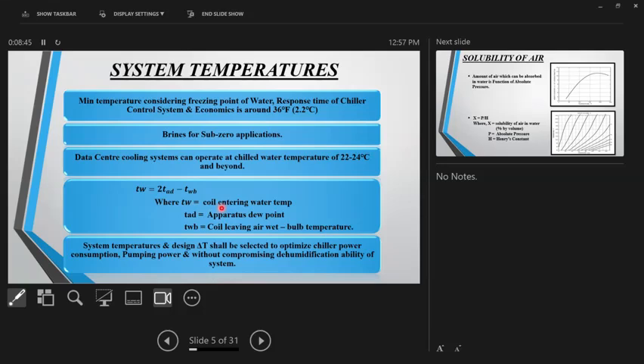TW was the coil entering water temperature. TAD was the apparatus dew point, or the anticipated coil surface temperature, and the wet bulb was the coil leaving air wet bulb temperature. So this is how tentatively we used to design chilled water temperatures for a given application. Now obviously there is not much use of this formula, because nowadays we have sophisticated coil selection softwares where you really don't have to go in any empirical way.